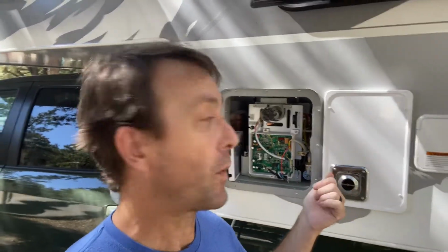But this one was to bypass the ECO sensor, and that would tell you the control panel was a problem, but that wasn't the case because we put it back together. I haven't changed the control panel. I have a brand new control panel inside the camper. So now it works, and all I can think is that somewhere in here there was a loose connection.